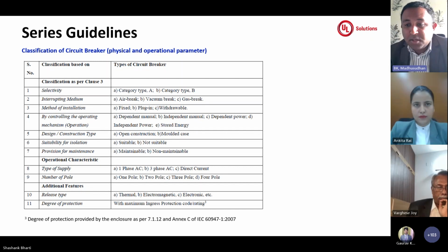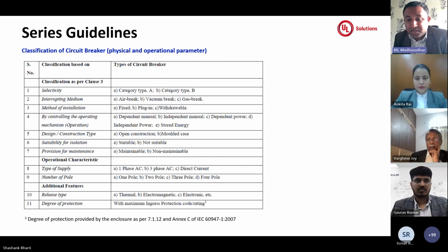And also based on the features inside, how the breaker operates, whether it may be thermal, magnetic, or electromagnetic, all the combinations you need to declare. And also at the end, you need to declare the ingress protection if you are using your breakers with any of the enclosures. So basically, with all these constituents for a separation of the frame sizes, and based on these declarations, the sample sizes will be selected and the number of tests will be done on the products. And that is where the guidelines come in, and these are the basic initial declarations that have to come from manufacturers at the time of submission. Yeah, next slide, please.